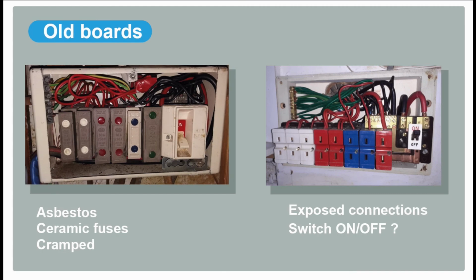You do have to take a view though on whether the old board you're going to use for your temporary supply is suitable for continued use. Take this one for example, another rewirable board, but this is an older type with ceramic fuses. I wouldn't want to use this board really. Few reasons. There's going to be asbestos possibly behind these fuses. When you pull them out, there's little asbestos flash pads. When you pull the fuse out, little bits of fabric and asbestos fabric can get into the air, and that's obviously bad for us. So I wouldn't want to use that.